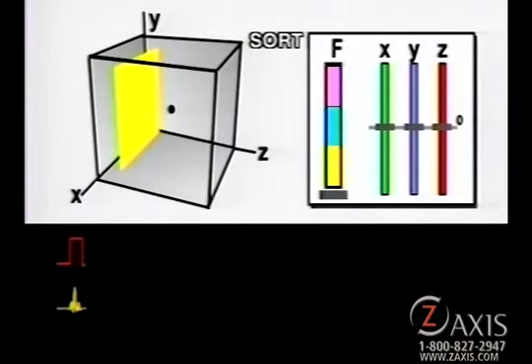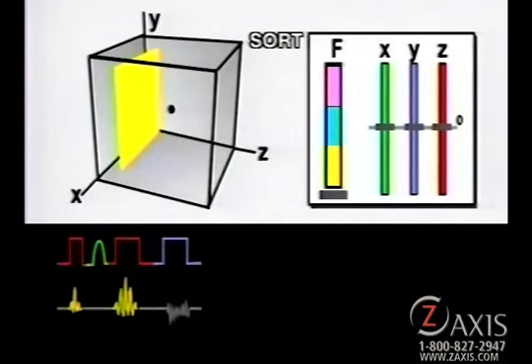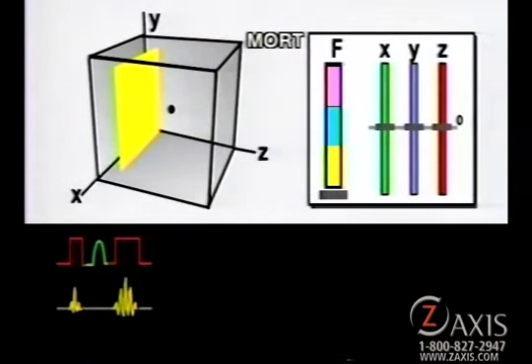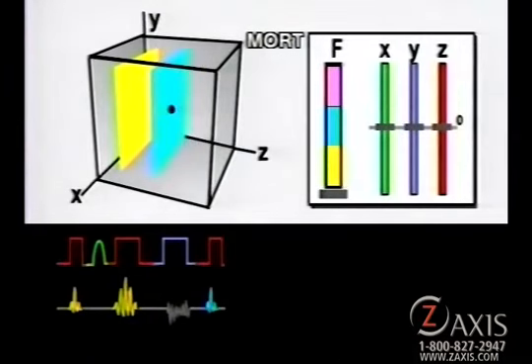In the single image orthogonal mode, the gradient coils are energized individually and only one frequency of radio pulse is applied. The image is taken from the left end of the scanning volume. In the multiple image orthogonal mode or MORT, the gradient coils are again turned on individually, but different frequencies of RF are used to move the image plane through the scanning volume along a single axis.